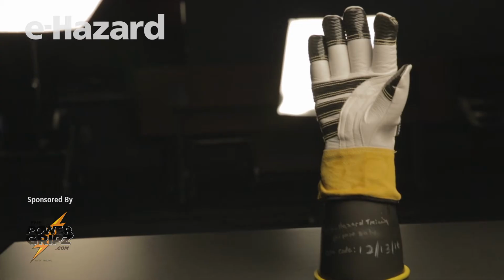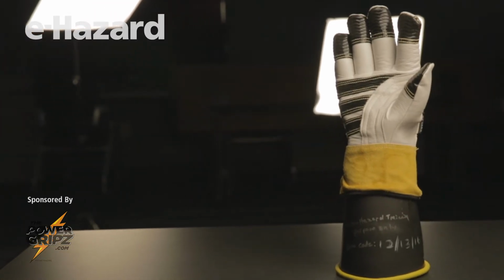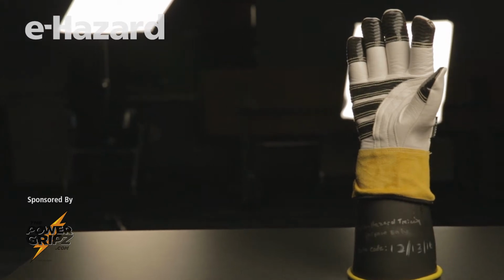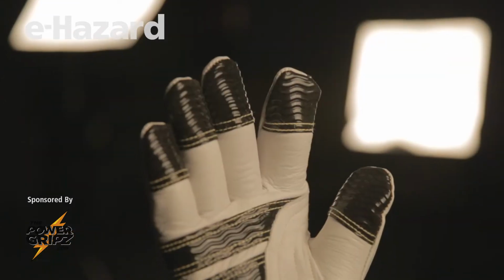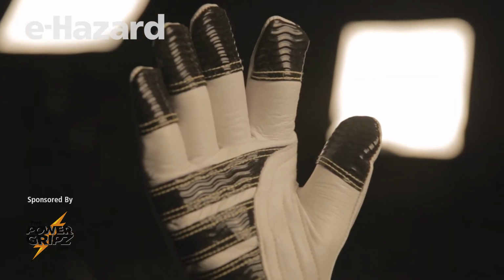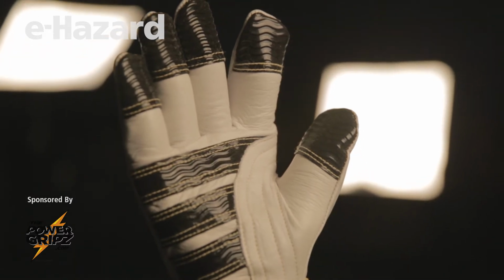There's a new proposed standard in ASTM to allow arc-rated protector gloves with multiple materials, but today the minimum standard, ASTM F696, requires at a minimum a specific tanning of the leather with a minimum thickness of that leather and a minimum of polyester or nylon thread. New gloves have come on the market with some modifications that, in our opinion, meet the minimum standard but add some features that may really be useful in the workplace.